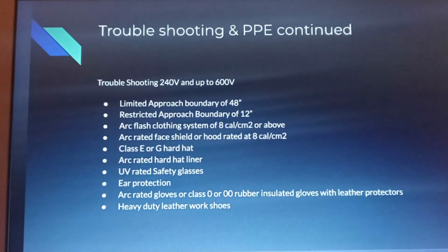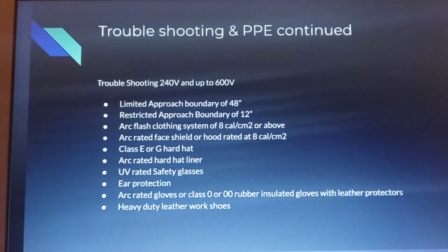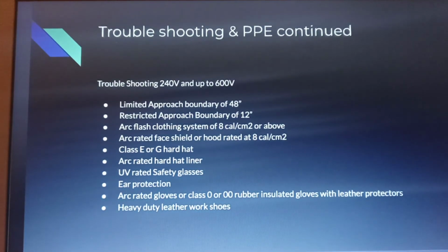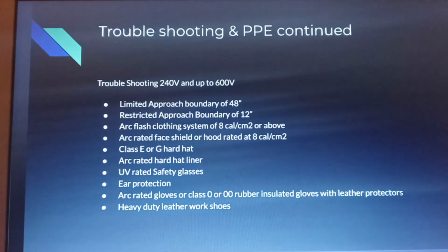And here's the big boy, troubleshooting 240 volts up to 600 volts. So the limited approach boundary is 48 inches. The restricted approach boundary of that is 12 inches. Arc flash clothing system needs to be at least 8 cal/cm² or above. Arc rated face shields or hoods rated at 8 cal/cm² or above. Class E or G hard hat. Arc rated hard hat liner, UV rated safety glasses, ear protection, and then arc rated gloves or class 0 or 00 rubber insulated gloves with leather protectors. And then heavy-duty leather work shoes are required.